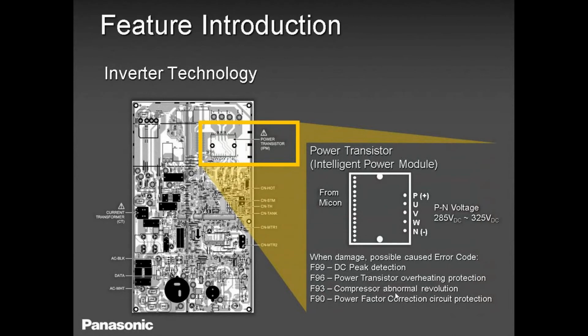there. This is basically your IPM module. Now it's not one board, okay, guys? It's not one board by itself. It's the entire PCB that, when you open up our outdoor unit, you will find as a complete board. That board, as I mentioned earlier, has a control side, a power side, and the IPM. That IPM board, which is this one here, a little small piece, when it goes bad, these are the error codes that you will expect.